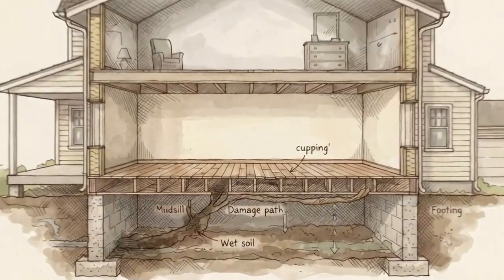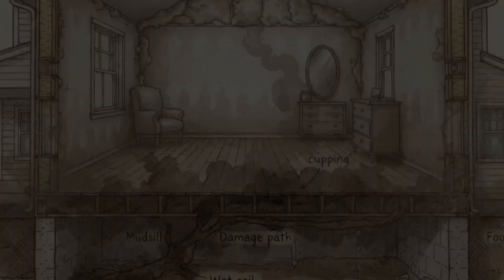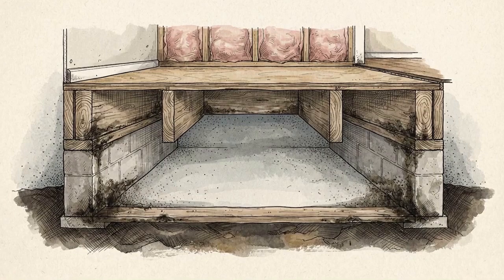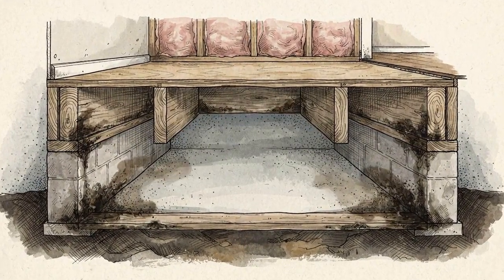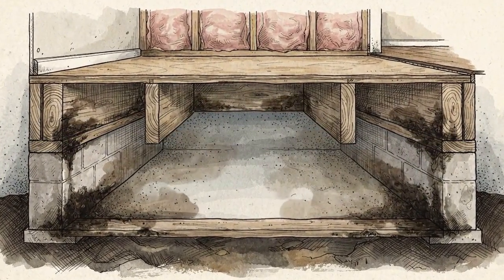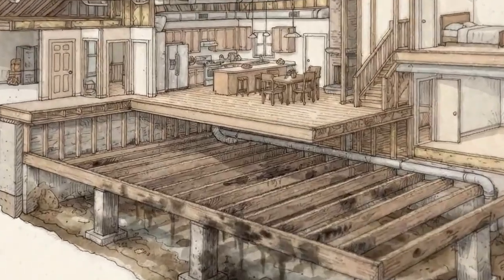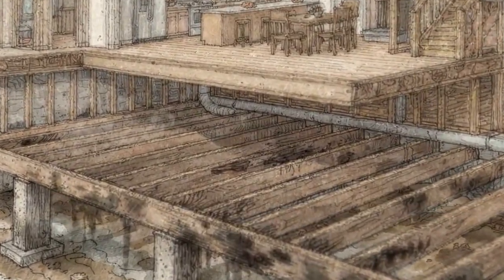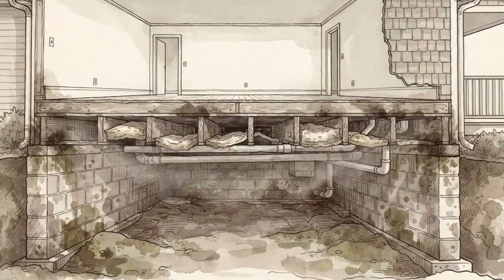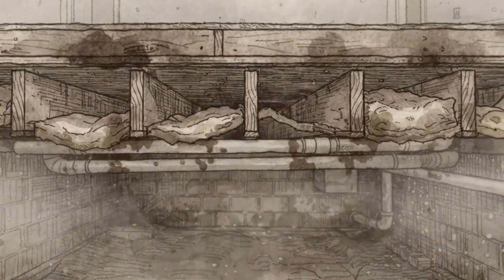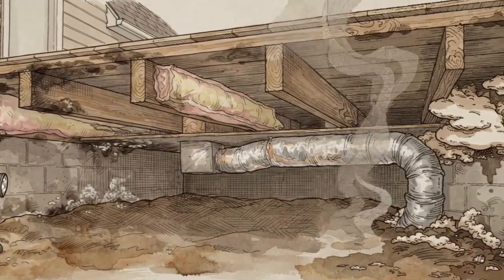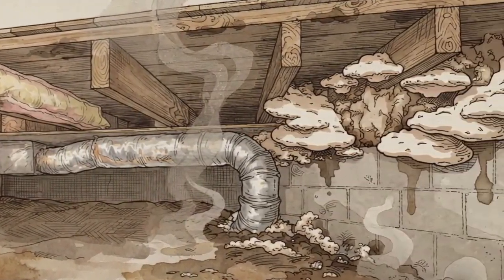The two seasons are connected through the physics of moisture, but the most urgent cost is the one that happens above the insulation inside your house. The Building Science Corporation has documented in field studies across climate zones 4 through 7 that a significant fraction of the air inside a typical wood frame house originates from the crawl space. The Building Science Corporation calls this upward movement the stack effect. It pulls crawl space air through gaps in the subfloor and around plumbing penetrations into the living areas above.